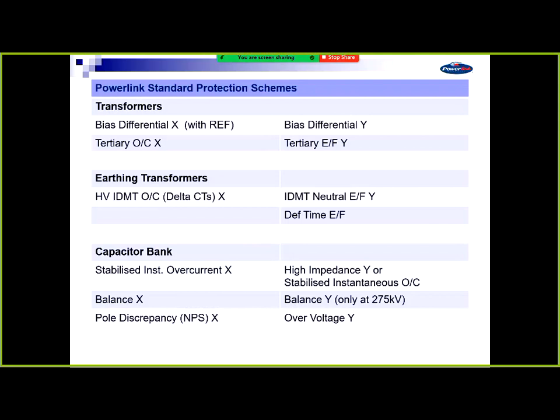So for the transformers, we start off with our X as a bias diff and a tertiary overcurrent, and the Y is just a bias diff and a tertiary earth fault. Earthing transformers have an overcurrent on the X and another overcurrent, neutral and definite time on the Y. Our cap banks have basically overcurrent and a high impedance or another overcurrent, depending on the voltage level that we've got. We've also got a balance protection, and there's a pole discrepancy on the X and an overvoltage on the Y for the cap banks.